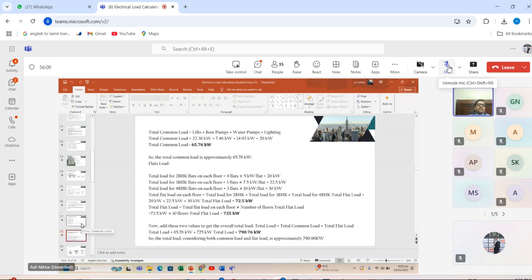I will show you in this presentation. Let's see. It is showing total common load is equal to lifts plus bore pump plus water pump plus lighting load. We have to add all these loads. Understand? Yes, sir. So we have to add all these loads: lifts plus bore pumps plus water pump plus lighting load. So the total common load is 65.76 kilowatt, approximately 66 kilowatts.